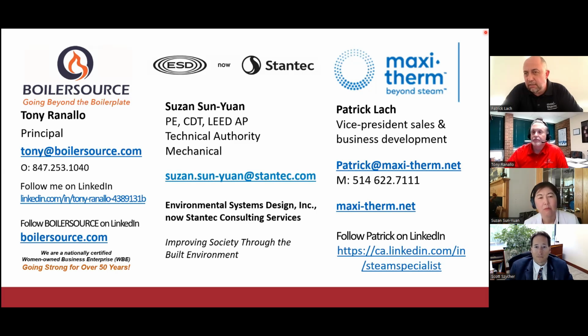Yeah, and one thing I'd like to add, Scott, is, hopefully on the call there are boiler operators or people involved with a boiler. If you can replace everything and go biomass or biogas or hydrogen, okay, great. But if you can do 10% of your steam with biogas or biomass, a small biomass boiler, because you have source fuel available nearby, that's a big gain today. So I think you can do it step by step. And by the way, same thing with waste to energy, because I want to push that, but you can go as low as 100 tons a day, compared to Minneapolis, which I think is more than 1,000 tons a day.